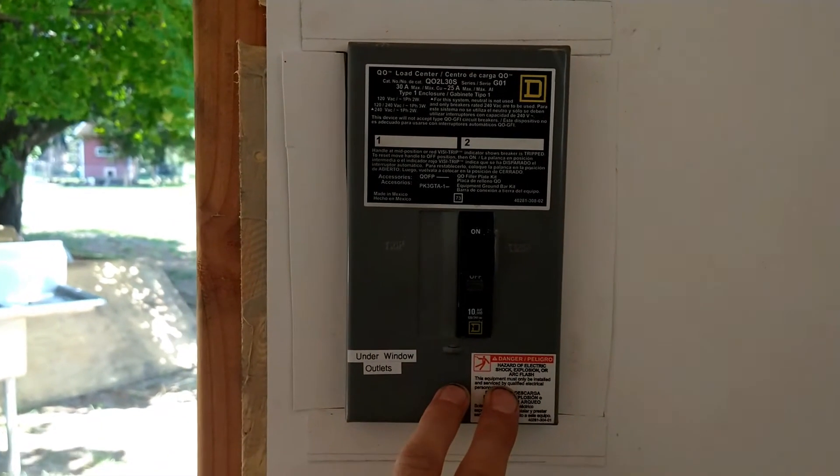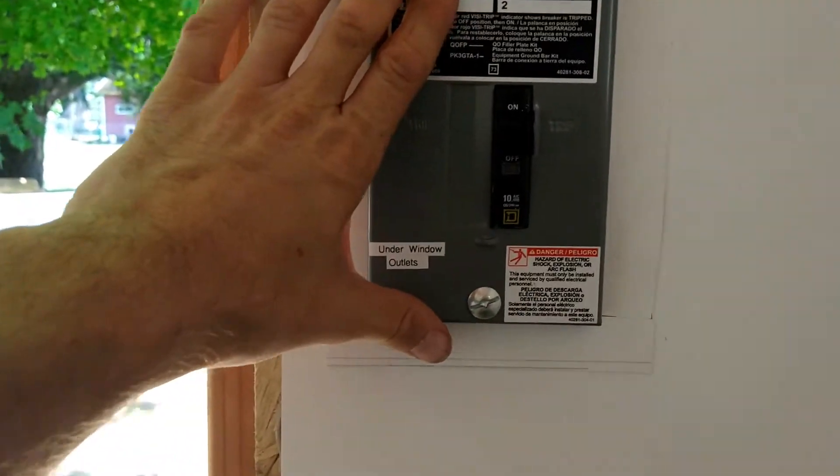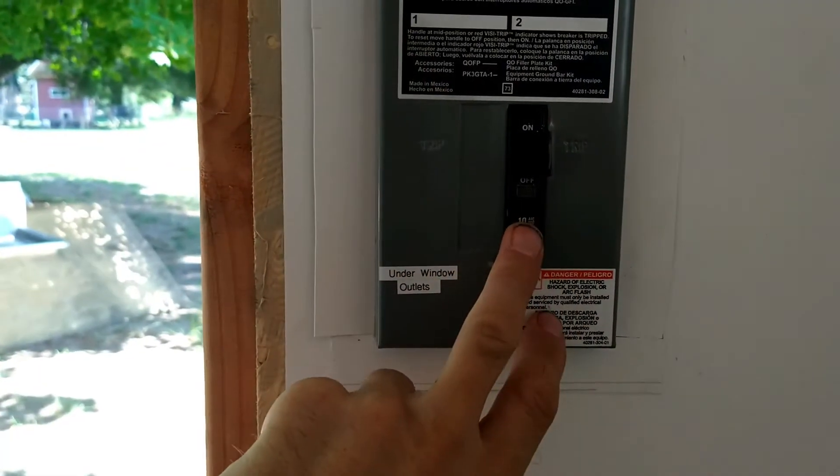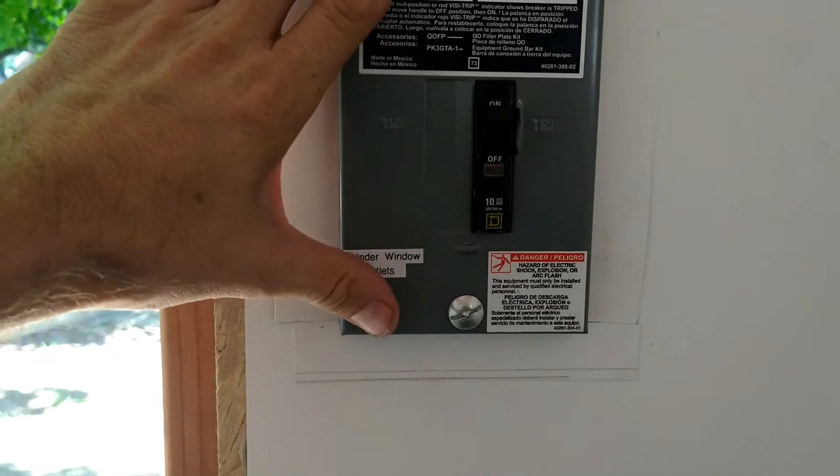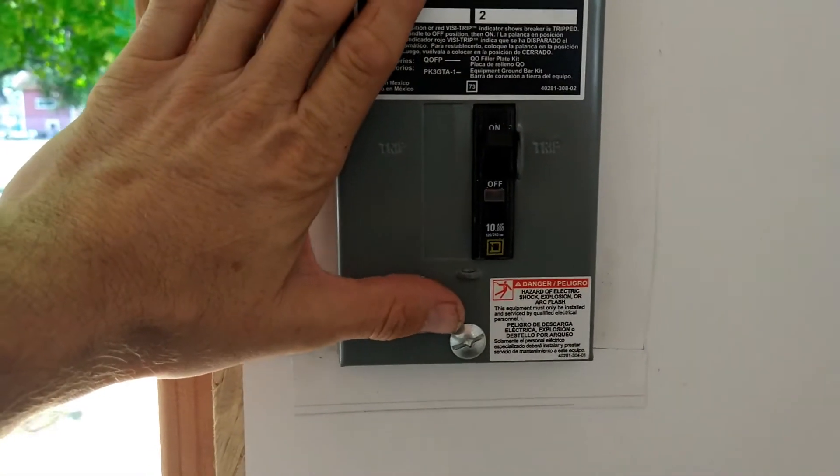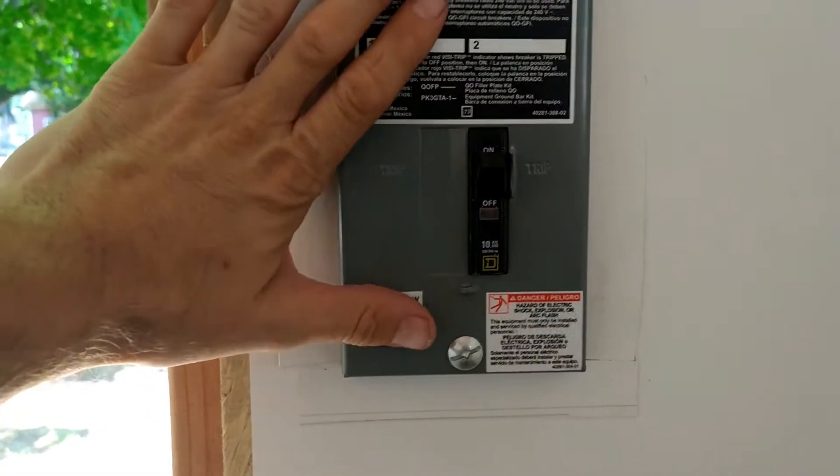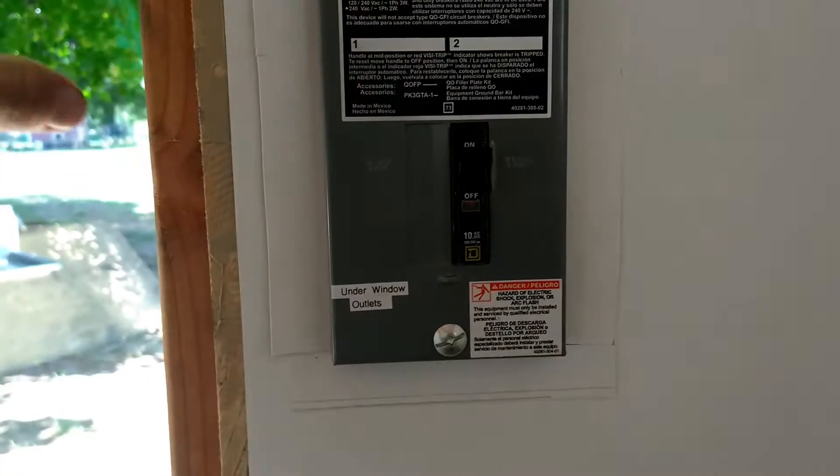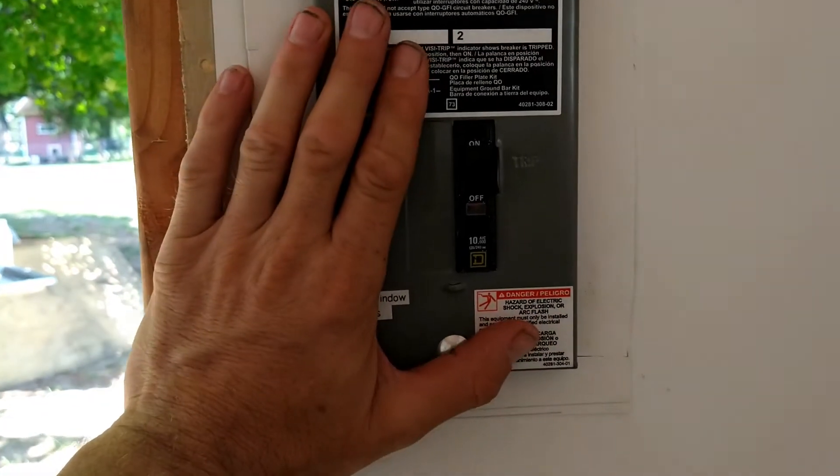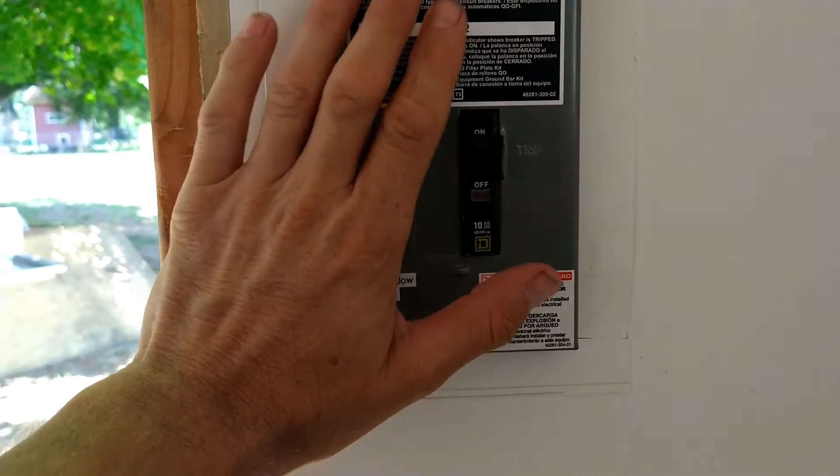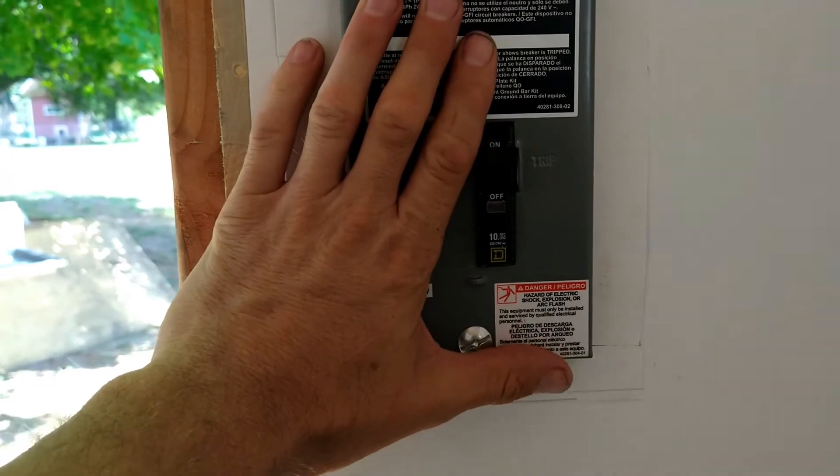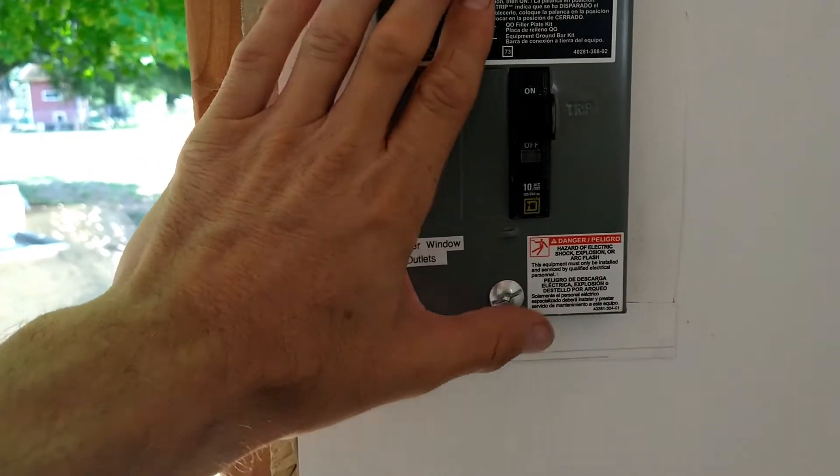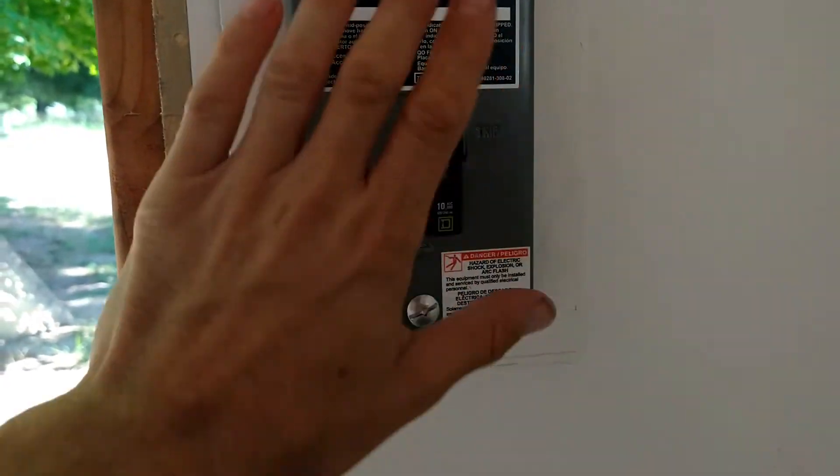This breaker, this disconnect, which I believe is a 30 amp disconnect with a 15 amp breaker on there. Because in case whatever he's hooking up to is only 15 amps, I didn't want the 20 amp breaker here to cause an overload at the 15 amp breaker that he's hooking up to at the residential or commercial location that is running the cord from. So we kept this at 15 amps for the breaker, and then this goes...